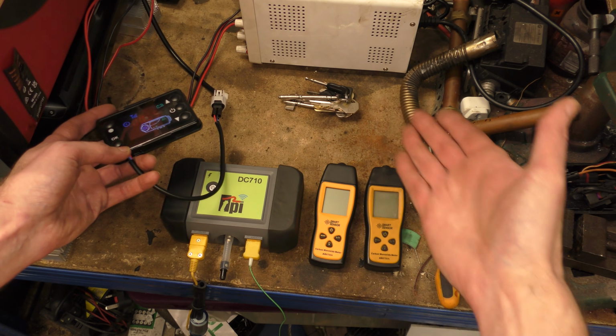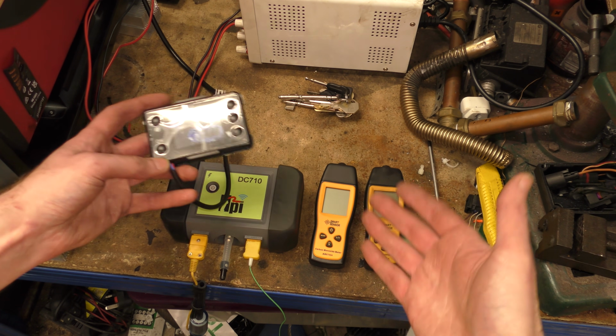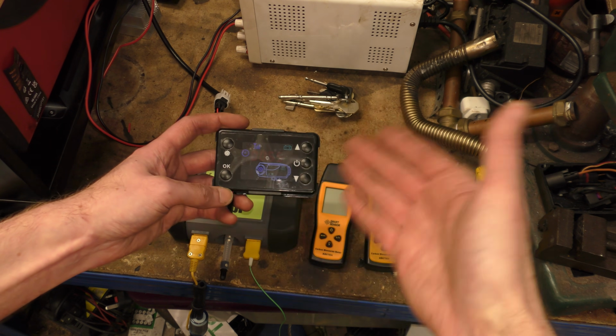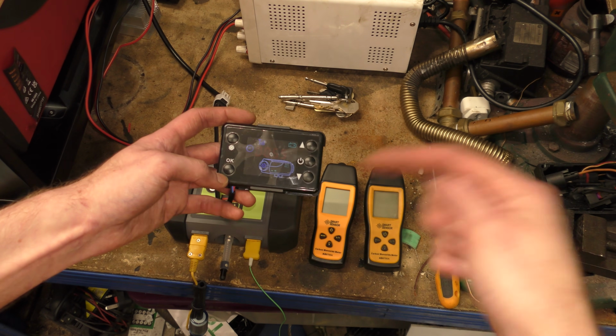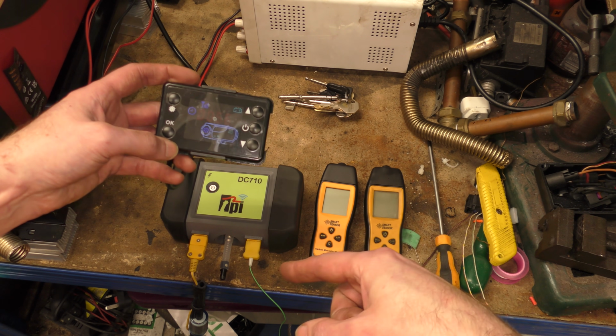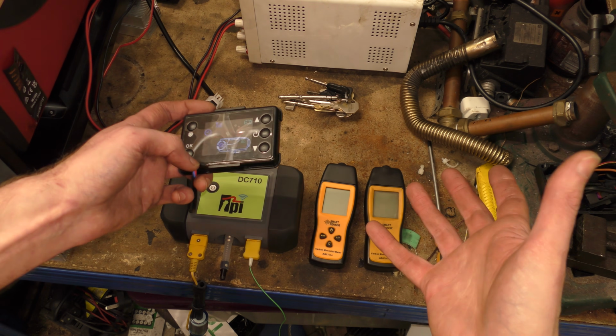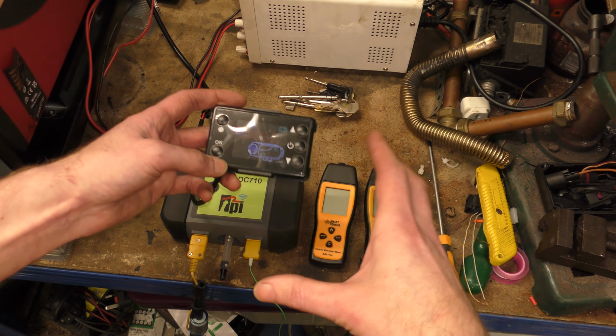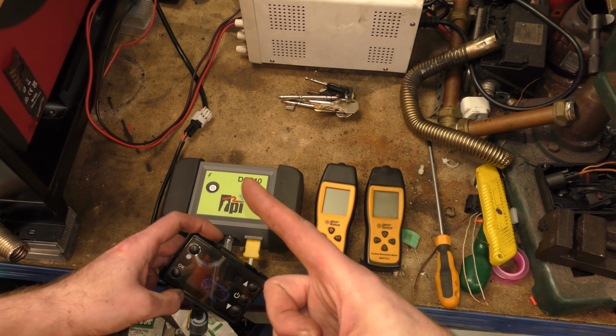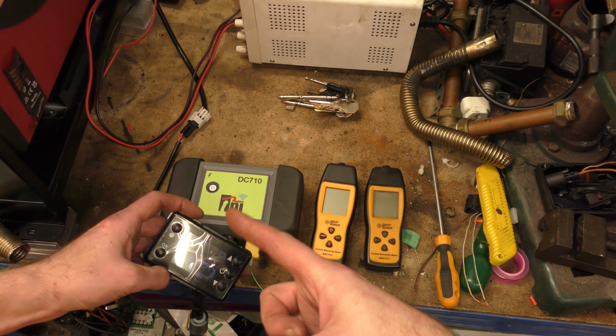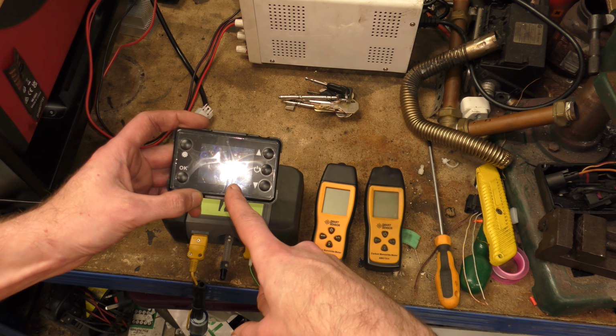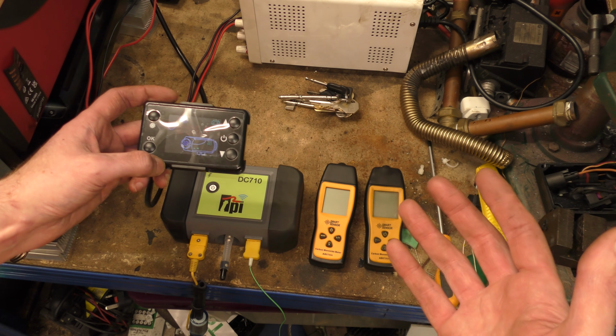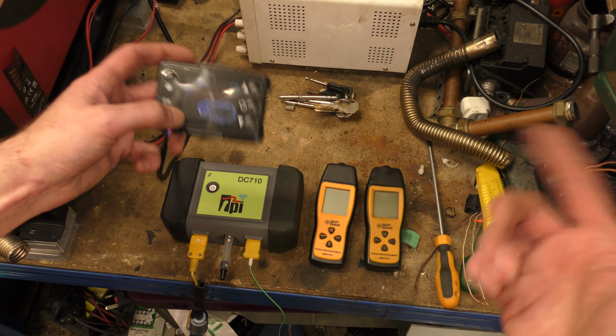So we'll start with a base reading of setting this to maximum and get a reading from there, then do it his way and take readings as we go to see how accurate his method is. The only problem is this heater took literally 5 minutes of no fueling to go down from 2 red bars to 1 red bar, so it's going to be a long process. I probably won't film all of it, just snippets as I adjust it and take the measurements.